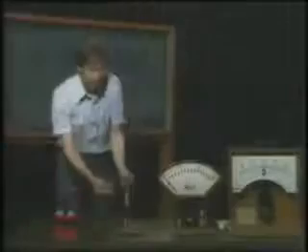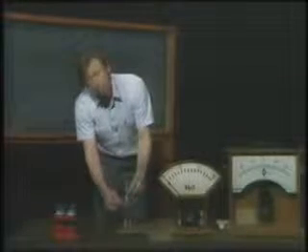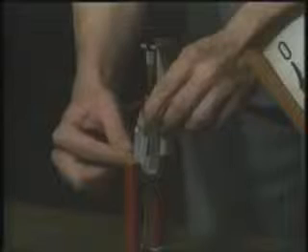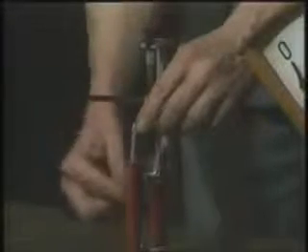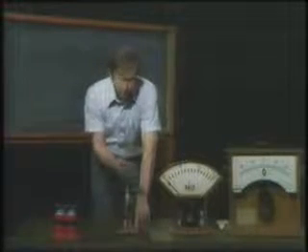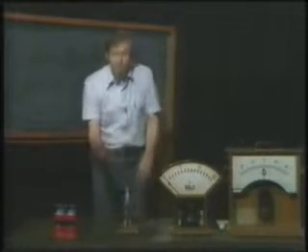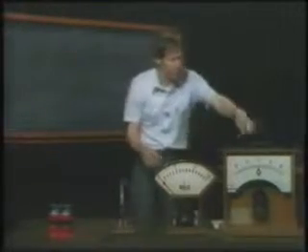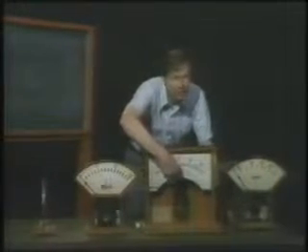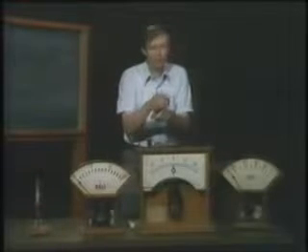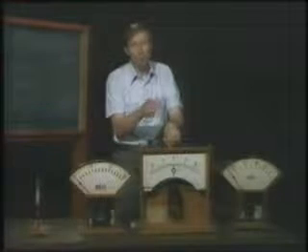The meter deflection is in the opposite direction when the current is reversed because the torque reverses. The magnetic moment is proportional to the current through the coil, producing a torque in the permanent magnet proportional to that current. So the galvanometer gives a deflection proportional to the current through it. The amount of deflection depends upon the spring constant — a tight watch-type spring that controls the balance between the torque and the meter's motion.